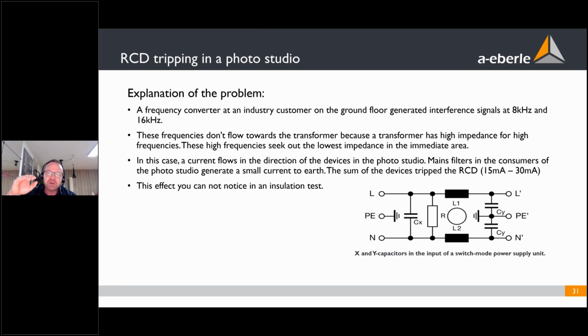And if this small condensator sees 8 kilohertz, 16 kilohertz on the voltage, there will be a small current going from phase to earth and neutral to earth. At the time the electrician switched off all the fuses, neutral and earth is still connected. So with the interference coming from a different company in this industrial area, we deliver 16 kilohertz on the voltage.